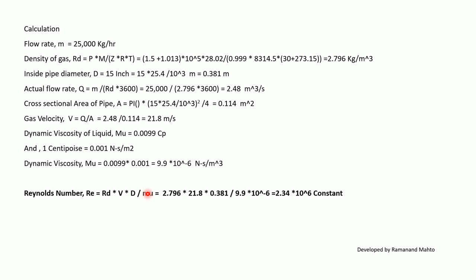Calculation: Flow rate M = 25,000 kg/hr. Density of gas: ρ = P × M / (Z × R × T) = (1.5 + 1.013) × 10⁵ × 28.02 / (0.999 × 8314.5 × (30 + 273.15)) = 2.796 kg/m³.